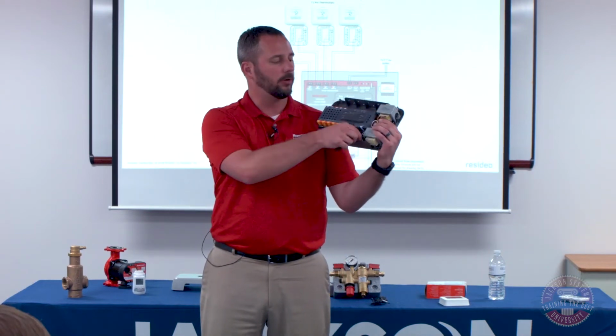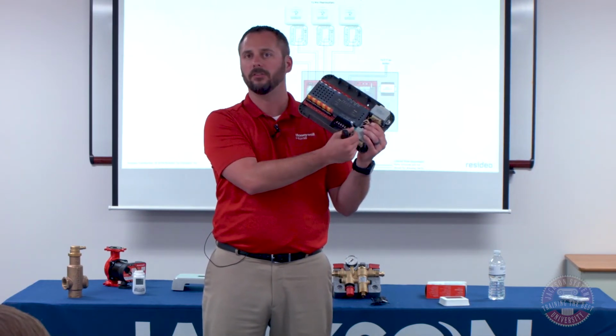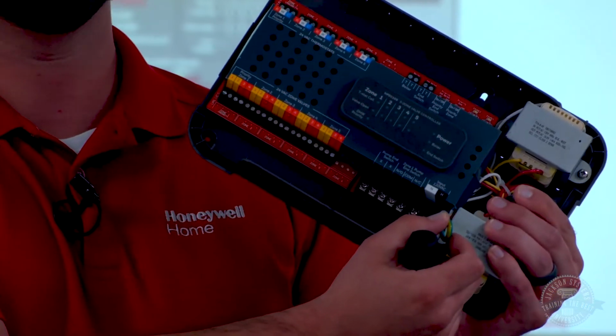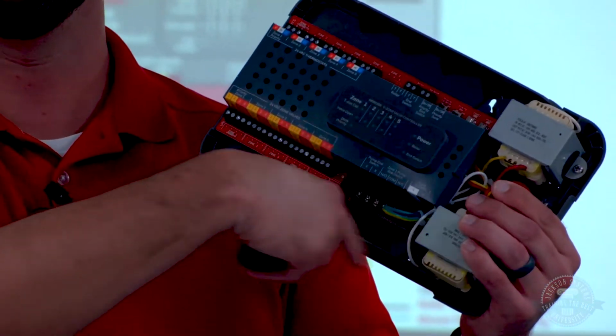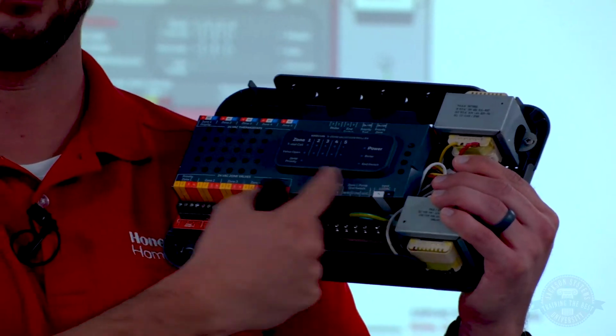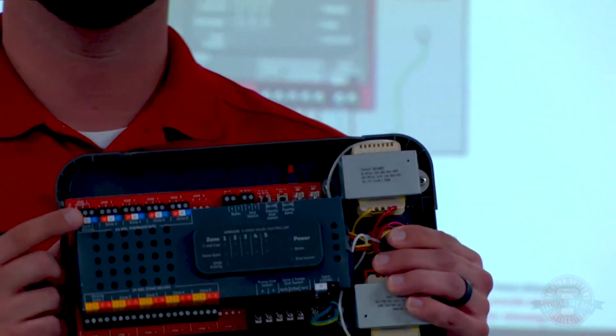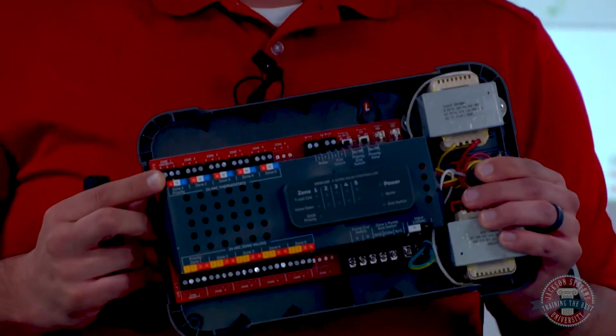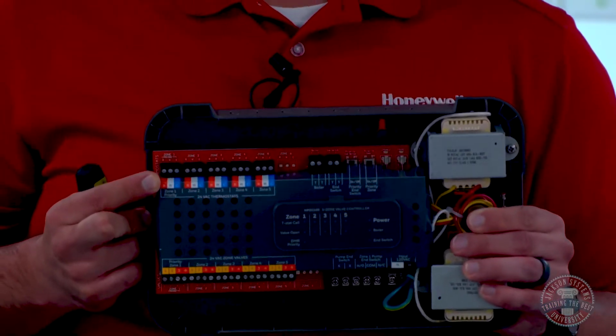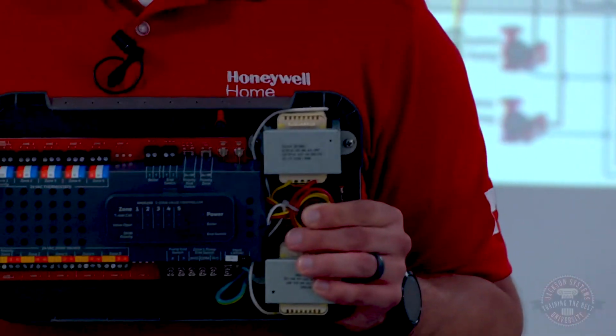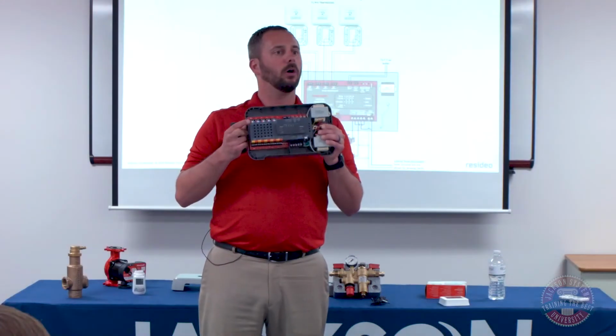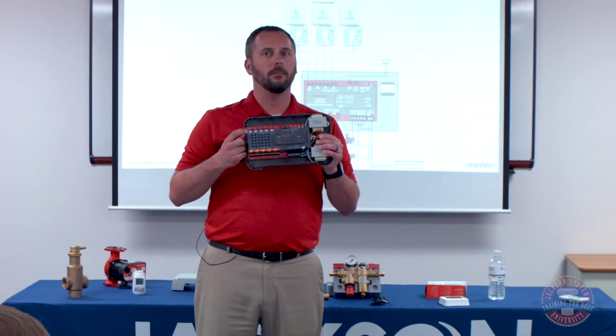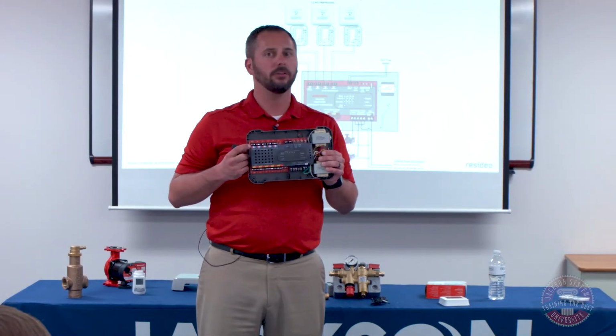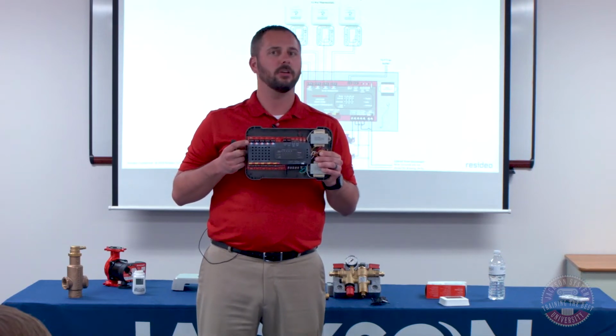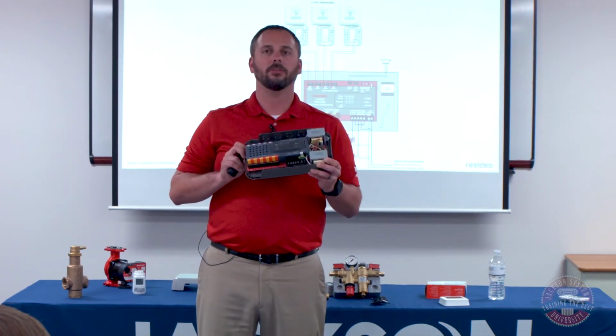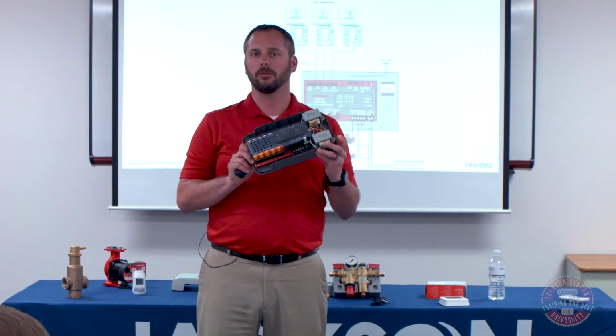We have also got a grounding wire on the zone valve instead of a grounding screw. So you've got a little bit more flexibility as far as running your wires through there, because this can get congested. We have one of the biggest selling features on this. We have the ability of running power stealing thermostats. So if you have a 2-wire power stealing thermostat, it will operate off of here. There's no need to come back and add resistors down the road if somebody changes it or add them from the initial install. We also have field replaceable transformers.